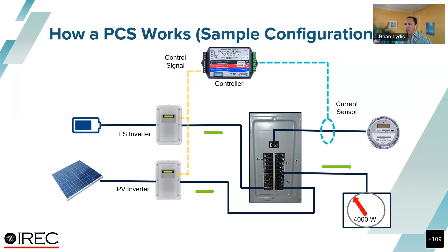So the power control system measures that inadvertent export. The controller measures that and then sends signals to the inverters to reduce their power, and they do so until there's no longer any excess export. Typical response times of these systems to reduce that power back to zero, or back to no inadvertent export, are on the order of several seconds, and they can be less than 2 seconds. So they're not extremely fast acting, but they can be fairly fast acting in terms of other grid interactions.